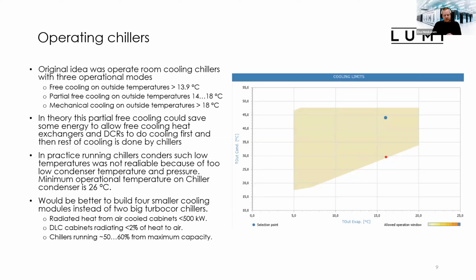So this was pretty much an issue after the first phase installation, when all of the compute devices were not yet in place in the data center. So we had some issues because of the low loads on the chillers to operate those. And also trying to operate with this partial free cooling was pretty much causing problems.